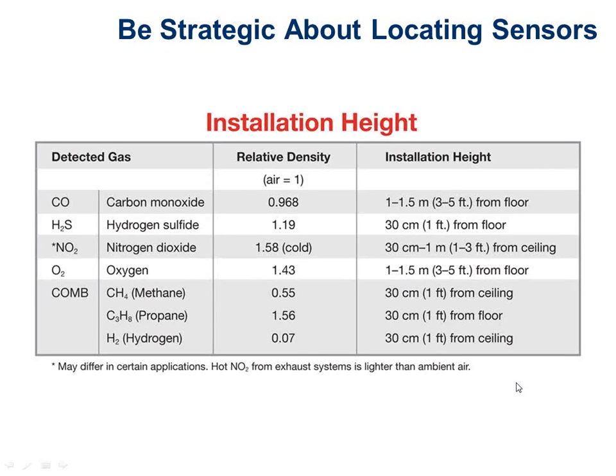In larger facilities like a parking garage, you can zone these systems out, just like you could a temperature control system, zone system, if you will. Or I can have different sensors on the different levels of the garage, spaced apart so I can get decent coverage. And then those can all report back to multiple or singular ventilation systems. I can have a staged ventilation system, or I can be ramping up a VFD. Nowadays, ramping a VFD is more common, right?